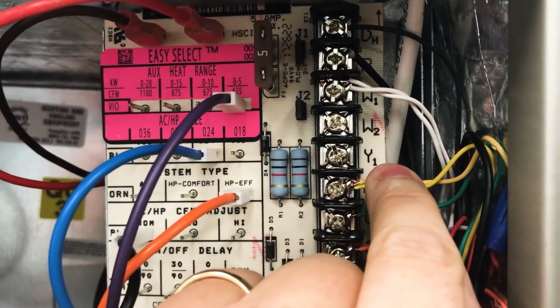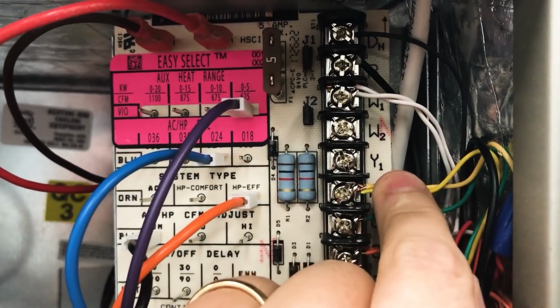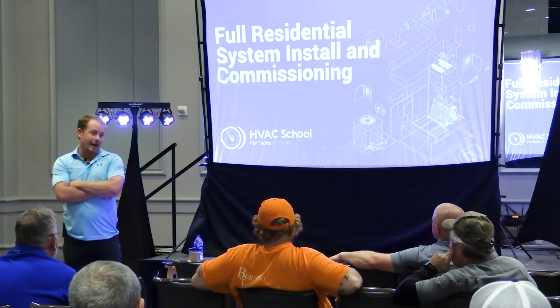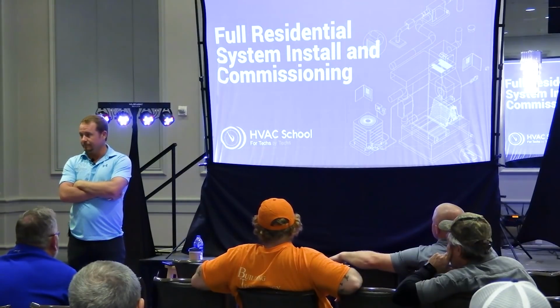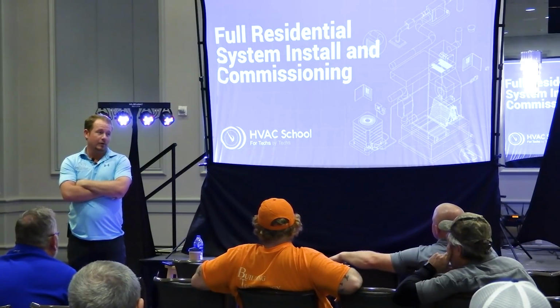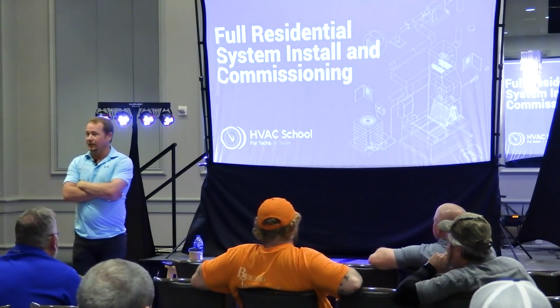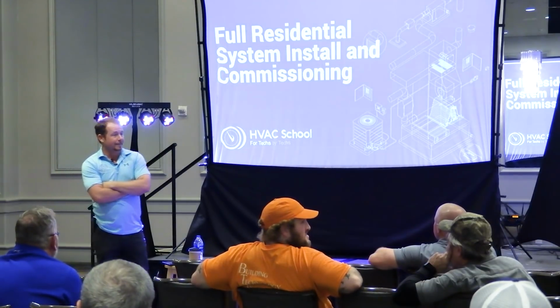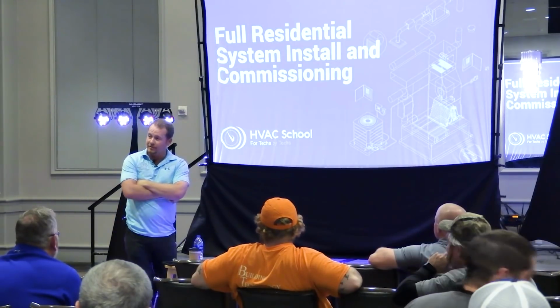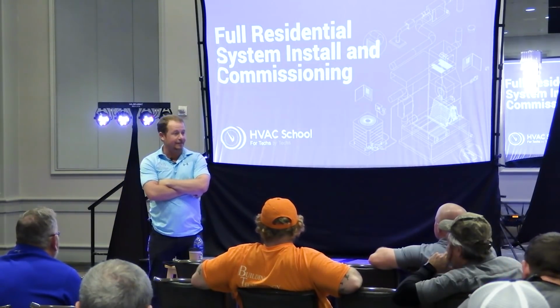Anybody ever seen that happen before? That never happens. Never. Of course, it happens all the time, right? What happens when they do that? Low airflow. You have low airflow, right? What's your static pressure? Low. So you go up to it, you're like, oh, look, I checked the blower charts. I measured my static pressure, and this thing is working amazing.